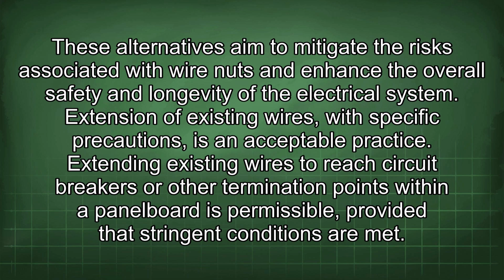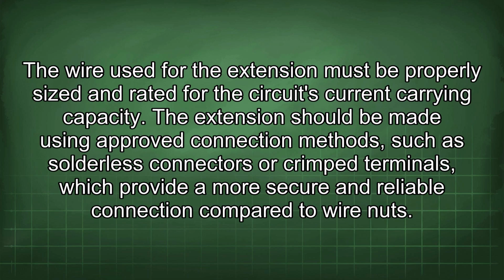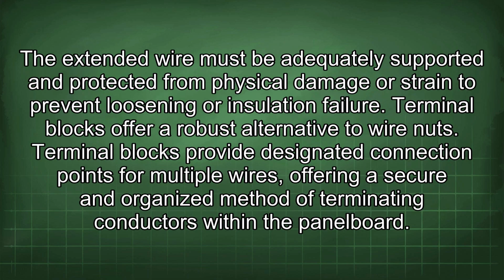Extending existing wires to reach circuit breakers or other termination points within a panel board is permissible, provided the stringent conditions are met. The wire used for the extension must be properly sized and rated for the circuit's current carrying capacity. The extension should be made using approved connection methods such as solderless connectors or crimped terminals, which provide a more secure and reliable connection compared to wire nuts. The extended wire must be adequately supported and protected from physical damage or strain to prevent loosening or insulation failure.